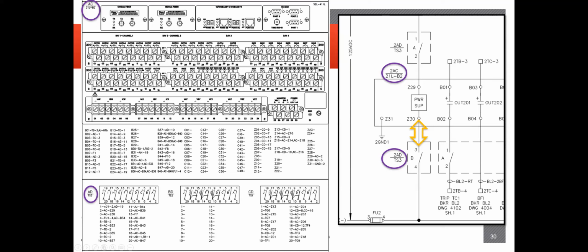As you can see, you can identify the test switches here, ADTS3, ADTS3, and the relay associated with it would be this entire block all around here. Identifying the points, Z30, if you're looking at this relay, you can follow along to see which block is associated with it. So we have the Z block here. If we go all the way down, you can see that it is in fact the negative side of the power supply, this number 30. Then going down to the test switch, you can see the B number 3 there.